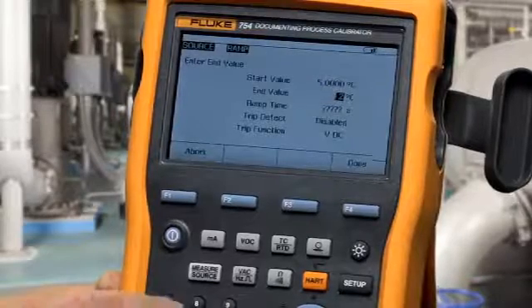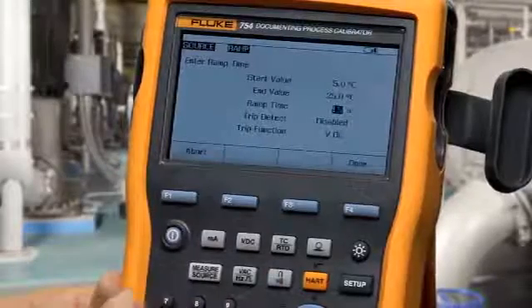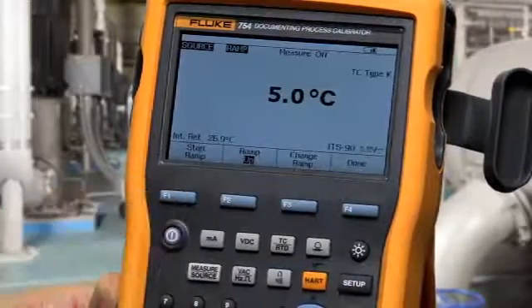Type in your starting value for the ramp, your ending temperature value for the ramp, and the amount of time that you want the ramp to take, say 15 seconds. Then press start ramp, and the temperature will ramp from the output into the indicator for your test.